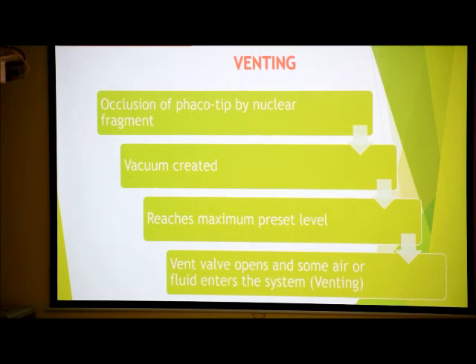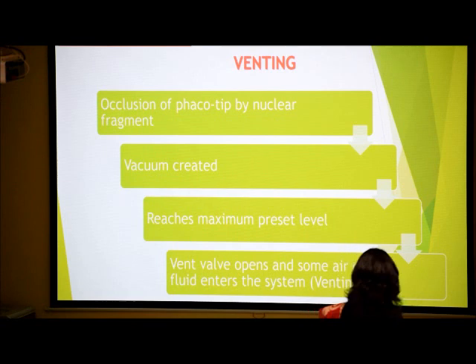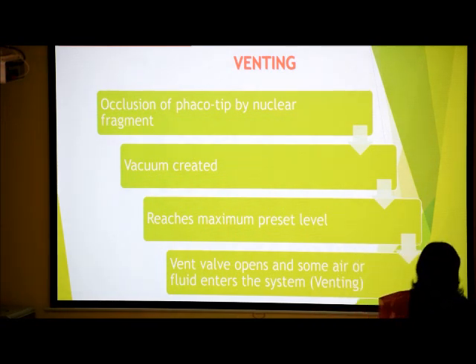Venting, as I have already told: occlusion of the phaco tip by a nuclear fragment, vacuum is created, and vacuum reaches the maximum preset level, the vent valve opens, and some air or fluid enters into the system. That is called venting.